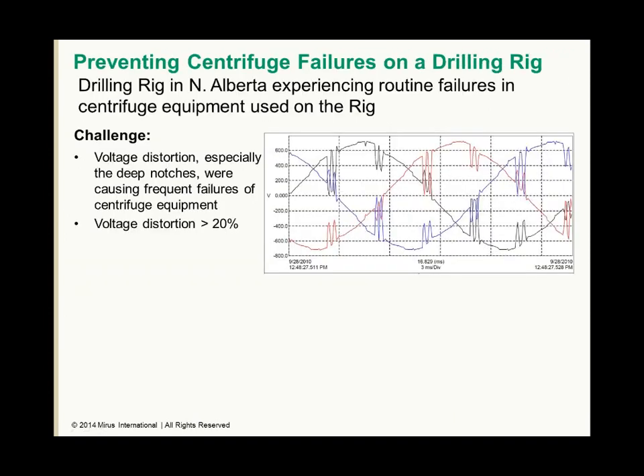We've done many successful projects for the oil and gas industry, including the application of lineator filters on all the drilling equipment for land and offshore oil rigs. But when harmonics are ignored, these facilities can have voltage distortion levels that exceed 20%, resulting in numerous operational problems and equipment failures. In these instances, we have successfully applied lineator harmonic filters as protection for the sensitive electronic equipment.